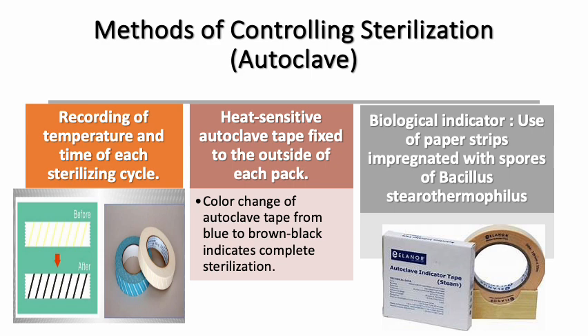stearothermophilus. Okay, again, the biological indicator for autoclave is Bacillus stearothermophilus. Now, the spores of the particular bacteria, placed in either a strip or liquid suspension in a vial, are loaded together with the material being sterilized. Now, after the cycle of sterilization, the indicator is then incubated and observed for growth. Now, if no growth is present, the sterilization cycle is successful.